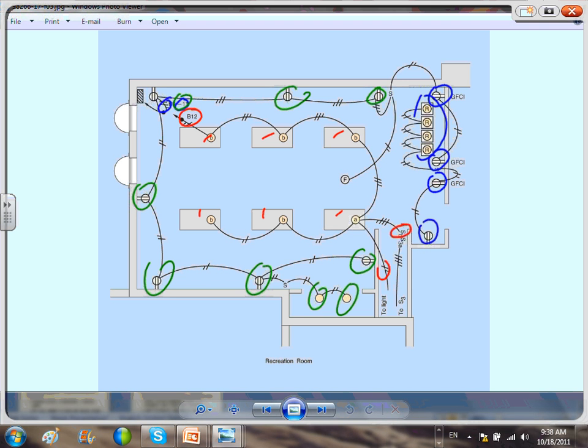When they reached here, there is a switch. How many receptacles do I need? I need a hot and a neutral coming to it, and out of it, a hot and a neutral going to the light. How about this one, need a hot and neutral to power it? And then the rest of them, that side here, guys, came and fed all these. There's a bar here. On the bar, the code says if you have a receptacle within 6 feet of a sink, any sink, you need a GFCI. So here's a receptacle. These receptacles are within 6 feet of the sink, so it has to be GFCI.